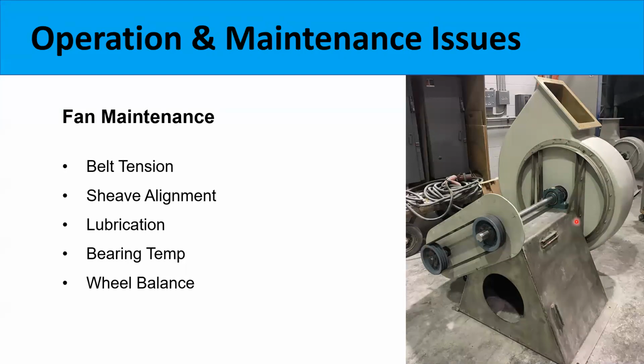This particular fan is a HEIL fan with a stainless steel base and a fiberglass housing and a fiberglass wheel on the inside. It's important to keep buildup off of these wheels. So there's an inspection port on the back side of this particular fan housing that allows you to go in and take a flashlight, periodically check that wheel for buildup. If you start to notice some vibration on that fan, then that's the first place we typically would go, is to look for buildup on that wheel.